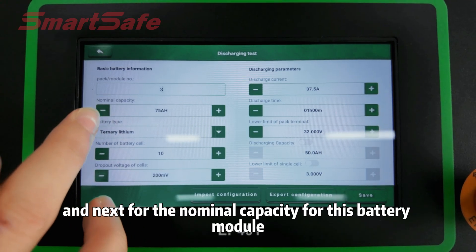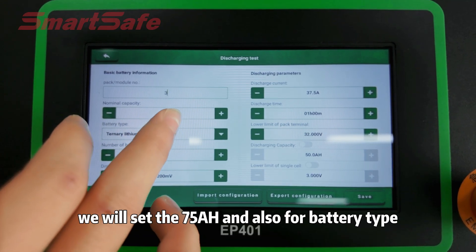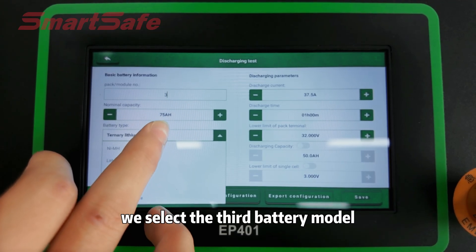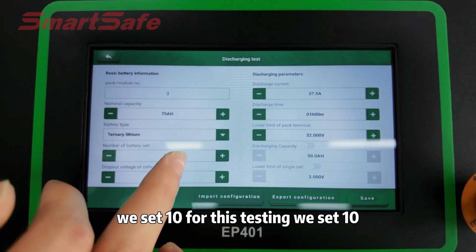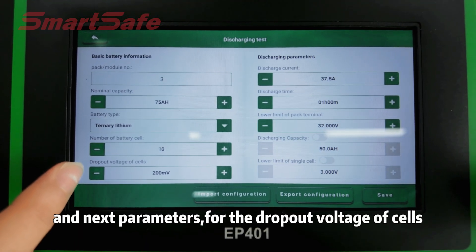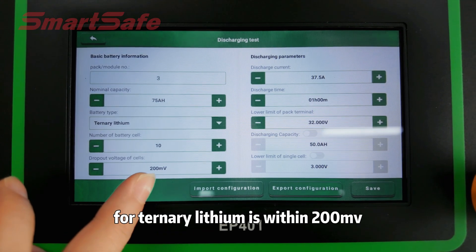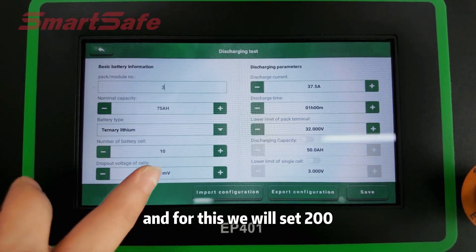Next, for the nominal capacity of this battery module, we will set 75AH. For battery type, we select the third battery model. For the number of battery cells, we set 10. For the dropout voltage of cells, the difference between cells is normal. For the battery module it's around 200 millivolts, so we will set 200.